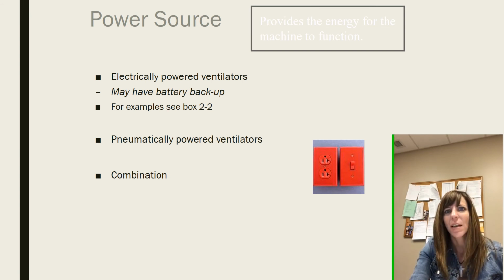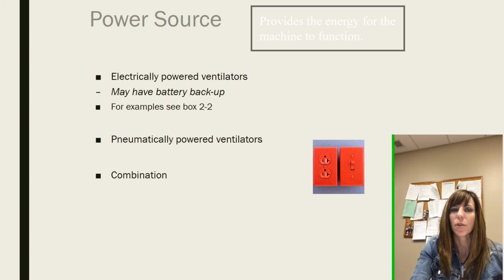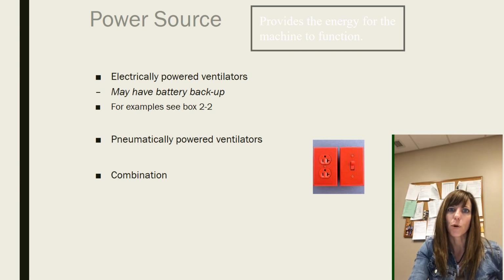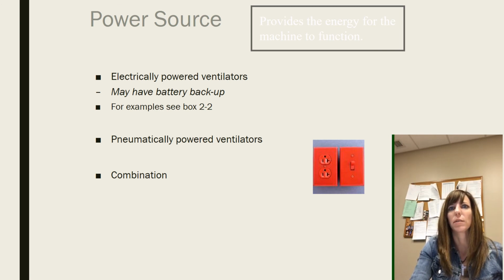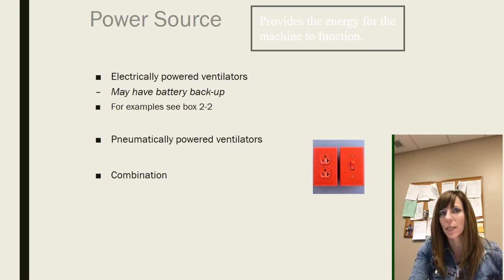It's pretty important. And then we have something called combined, which means you have to plug it into the gas source and plug it into an outlet, which is what you guys have in the laboratory setting. That's called the combined. And combined ventilators are often used with a microprocessor or a computer. The computer does all kinds of things for you. It shows the waveforms, it shows when the breath starts, it shows when the breath ends, it does the timing, and you can check the trends, which means you can go back over 1 hour, 2 hours, 12 hours, 24 hours, whatever, and see what the patient's been doing. So you can see what the compliance was yesterday compared to what the compliance was today, that kind of thing.